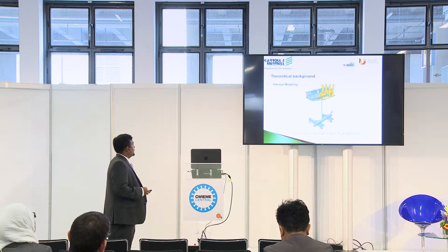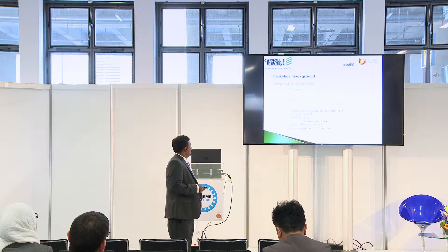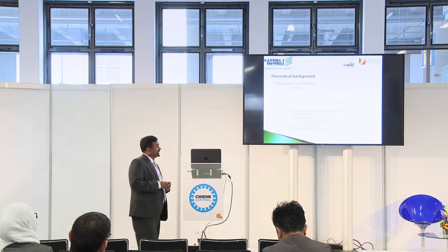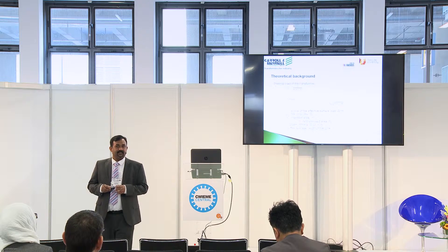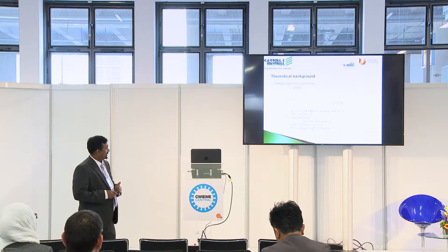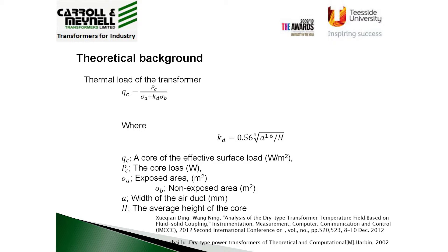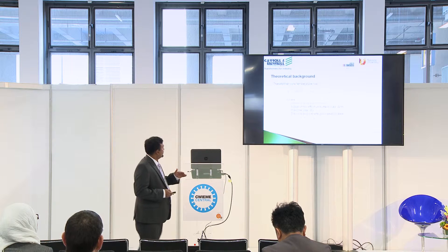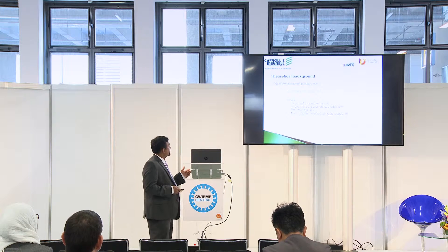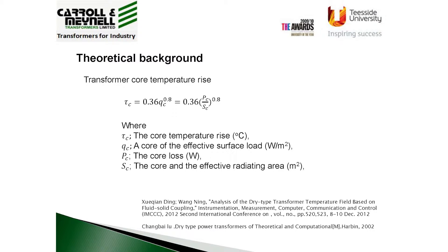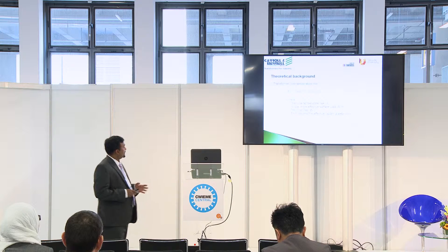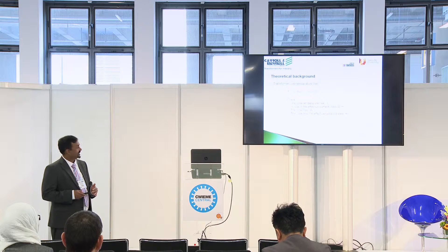This is the 3D model we created for this transformer before construction to make sure it meets the level we want. When studying the thermal aspects, we define a thermal load factor, which is related to the effective core surface load, the core losses, the exposed area, the non-exposed area, and so on. We use that to define the transformer core temperature, and it also includes some empirical data based on historical data collected in the company.